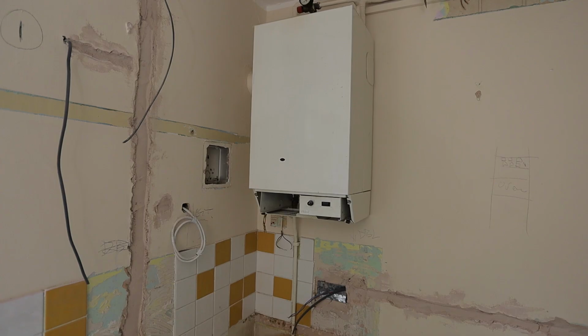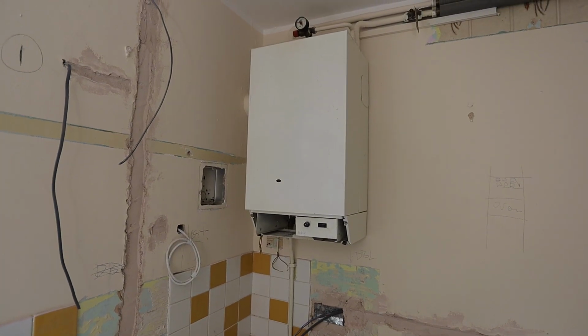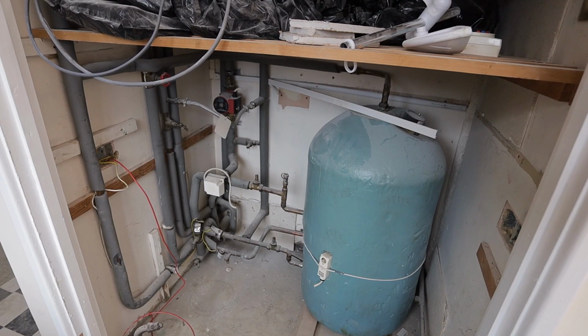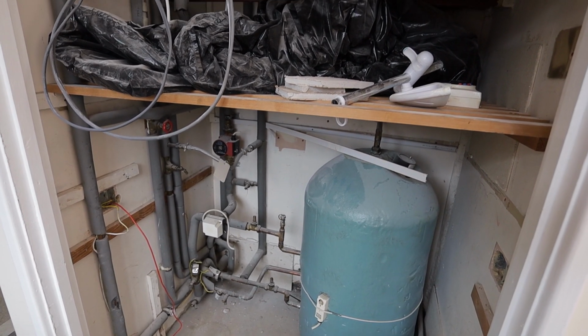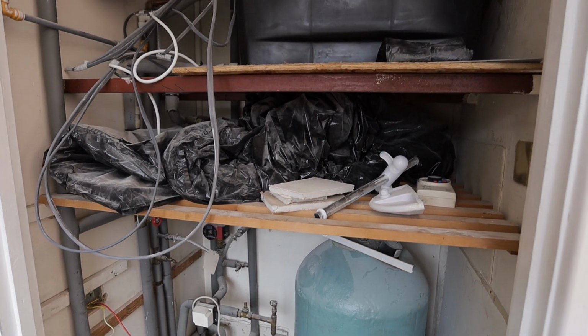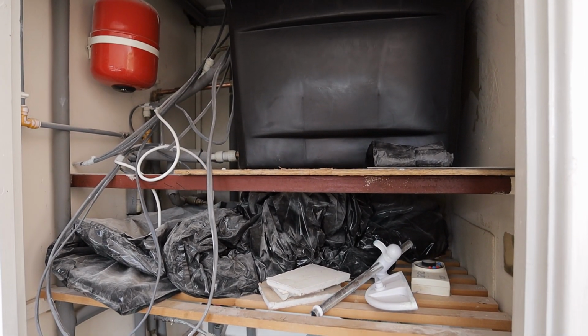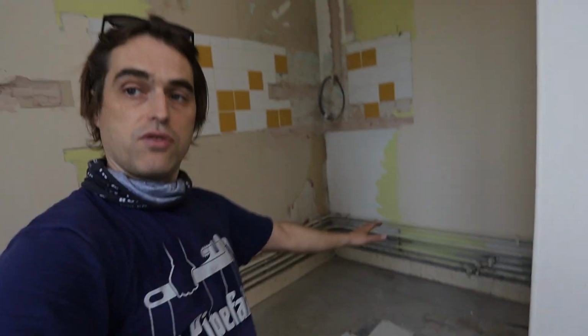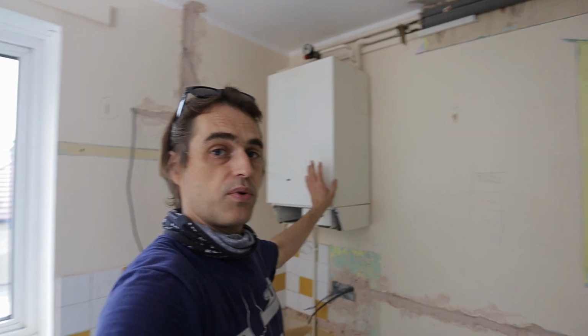Today I'm starting a full central heating installation in a one-bedroom flat in Kingston. What this property has at the moment is an old heat-only Ideal boiler, and we have a vented hot water cylinder here. So I'll be taking all of this lot out, converting this system into a sealed system. All those pipes you see right here, all of that will go. The boiler will go as well, and I'll put a new combination boiler on this wall right here.